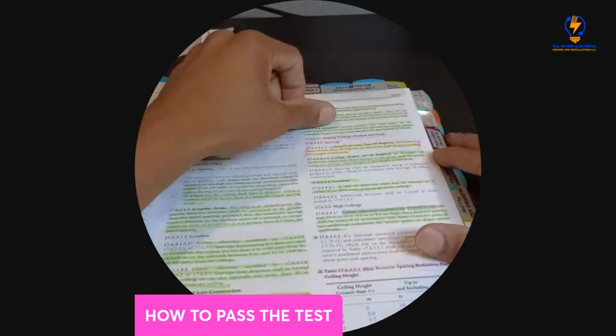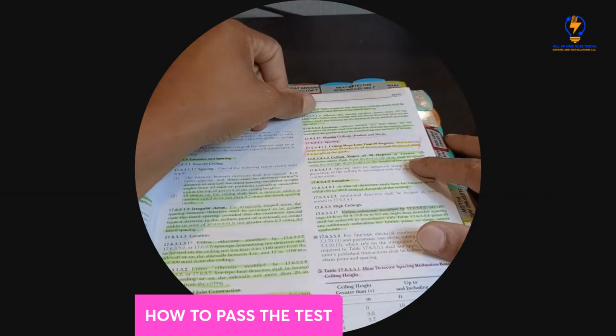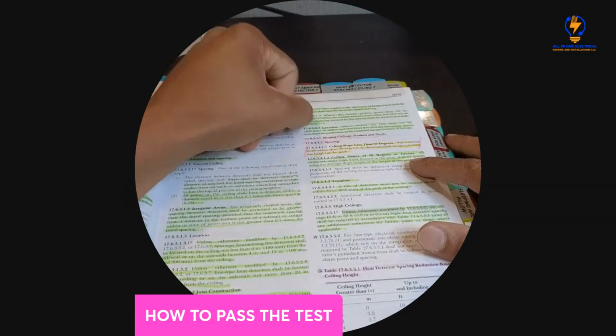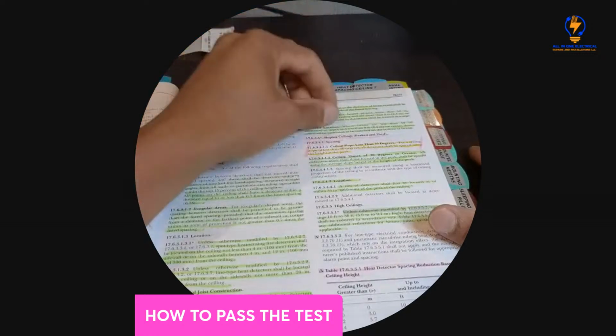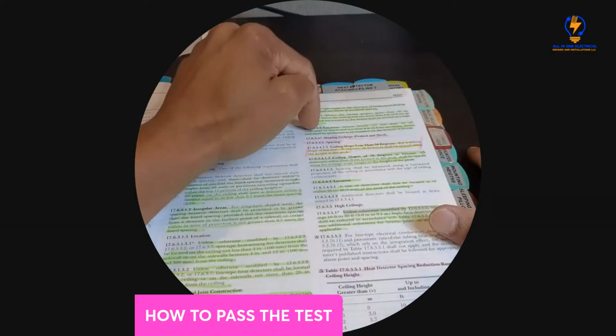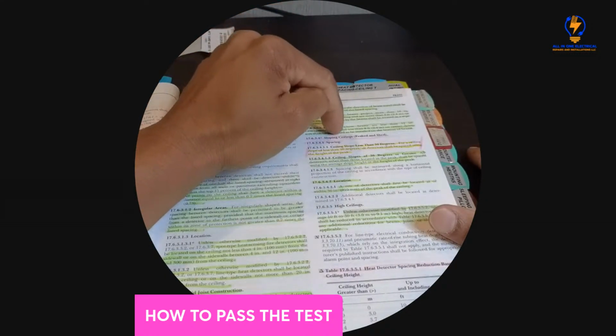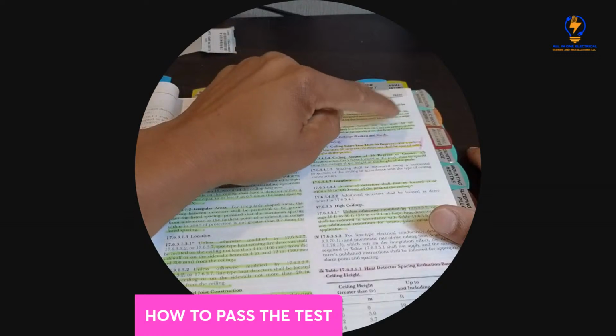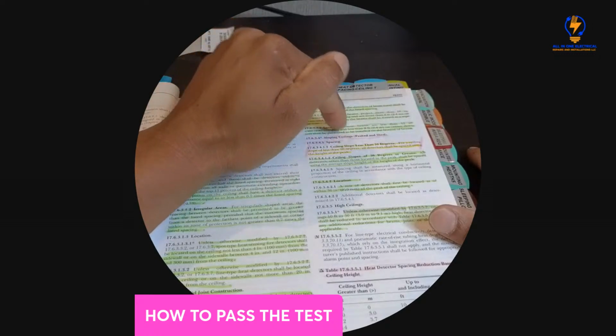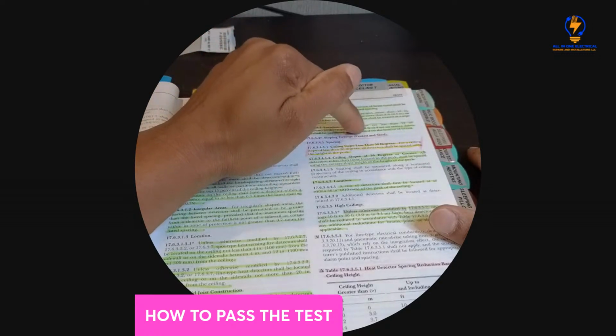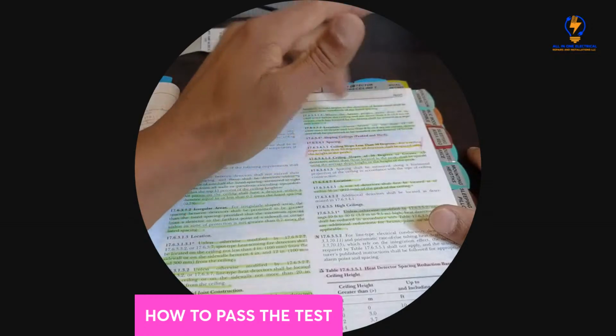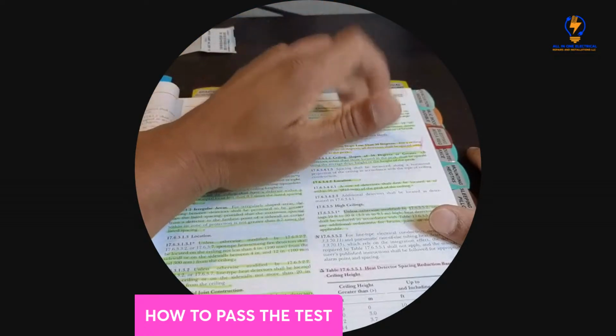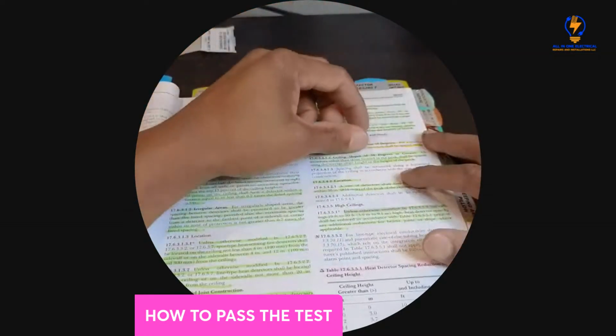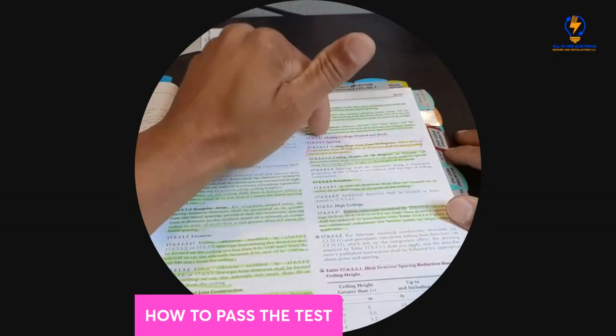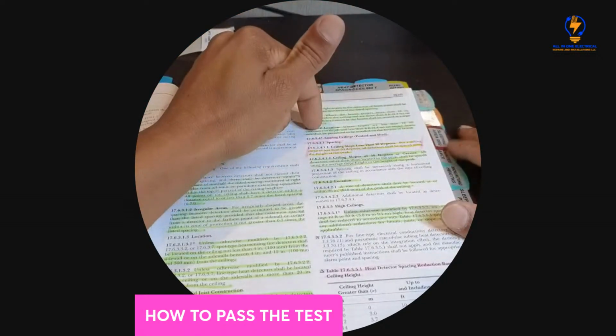So right here also locations. If you move to the side of the page, locations, very important. This one, where beams are less than 12 inches in depth and not less than 8 foot on center, detectors shall be permitted to be installed on the bottom of the beams. So this could be a test question as well. Okay, guys.